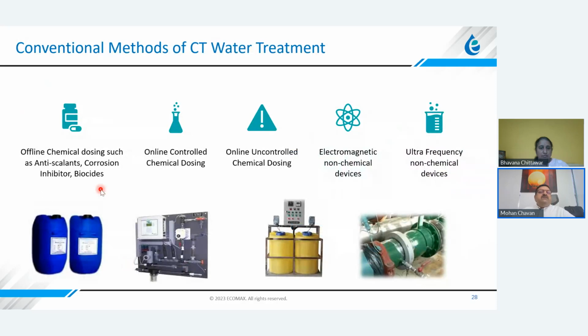Conventional methods that are used are basically the offline chemical dosing, which is done in the cooling towers, that uses antiscalants, corrosion inhibitors, and biocides. So here the dosing is done manually. There are cans like this, you can see everywhere near the cooling towers. There are some systems which are skid mounted, with online controlled chemical dosing. So there is a skid, there is a controller, there are some sensors to control the conductivity or the TDS of the circulation water, and accordingly the chemical dosing is done in proportion. It's the controlled chemical dosing.